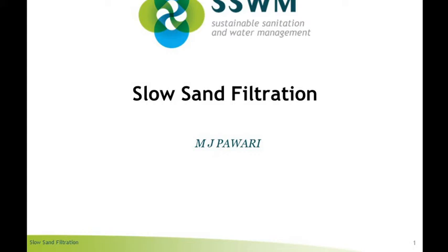In the filtration process, filtration occurs in four stages. The first stage is mechanical straining, where the suspended particles cannot pass through the bed of sand. They are trapped and removed by this action, called mechanical straining. The second action is sedimentation. Due to the presence of voids between the sand particles, they act as small sedimentation tanks, and impurities are arrested in the voids of the sand particles. The colloidal matter is removed by the process of sedimentation.